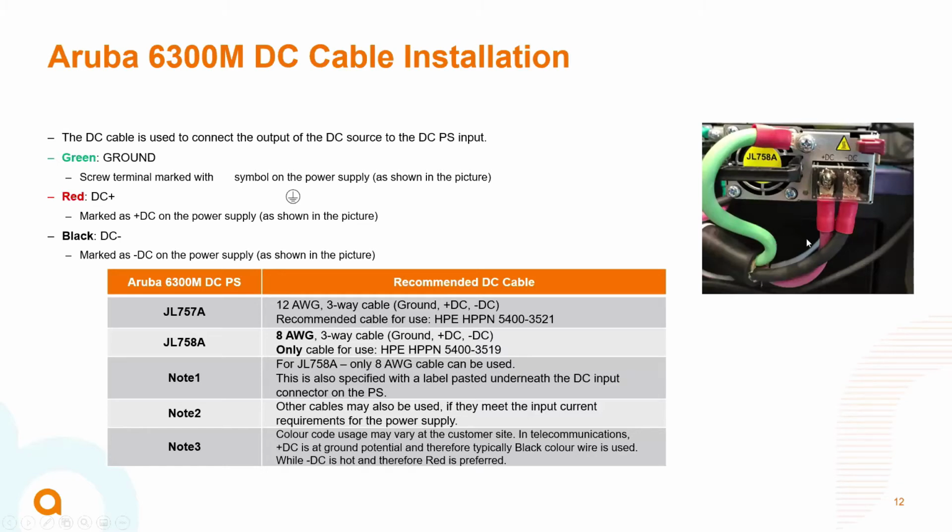During that time, the question you have to ask is, which wire is meant for the hot, right? Here, hot means red, we all understand. It's a little pinkish here, but consider it red. This is what you connect to the plus. On the black, you connect the minus. This green cable is a must. You must and should connect this to the ground. And you can see some of the notes here.